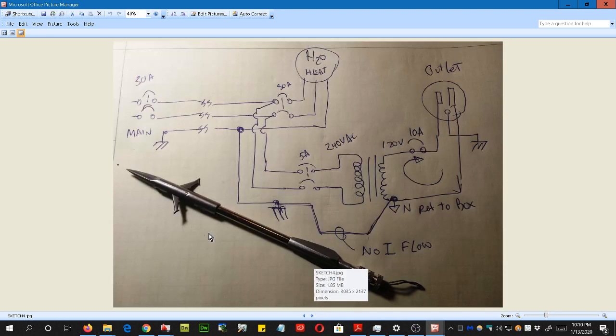Here was my solution for what Rick has, trying to build off of what you got. So he wants to be on the high side of the breaker here, which is good. That way he can have the light on, and when he turns the hot water heater off, by opening the breaker, using it as a switch. So I pulled 2 wires off of there. Here's my load going down here to the front side of this transformer. So I current protected here with a 5 amp double pole breaker. So he's got his 220 or 240 here. So my return path is from phase 1 through the coil, then back around to phase 2.